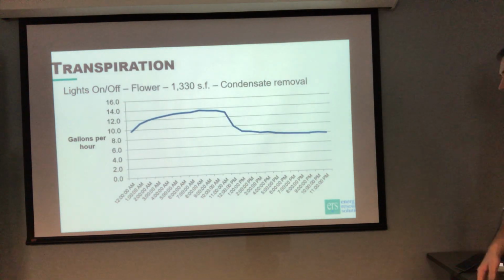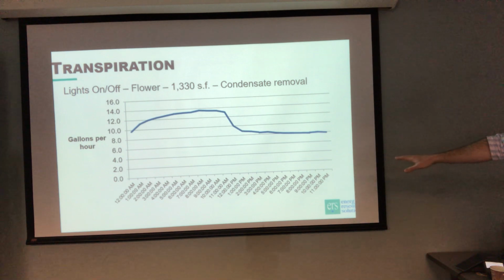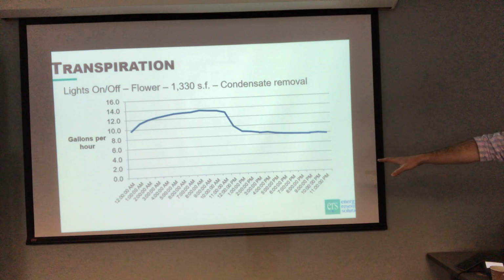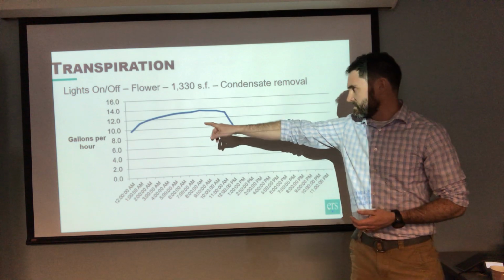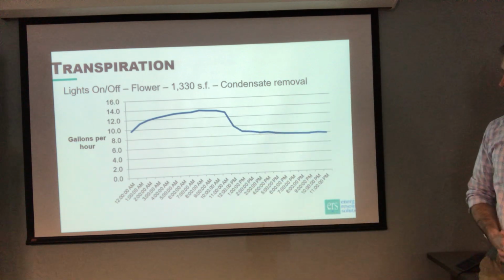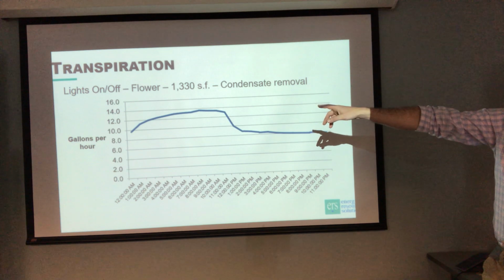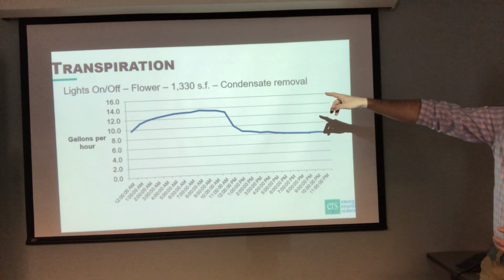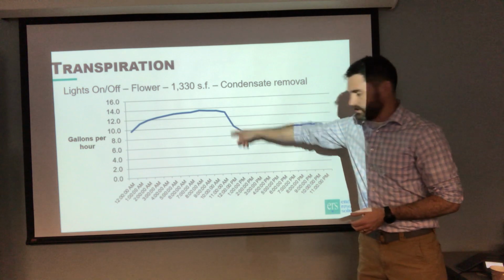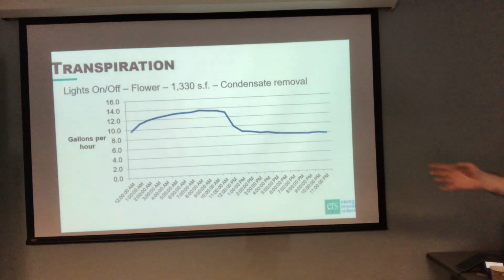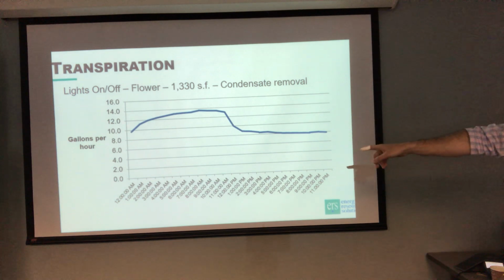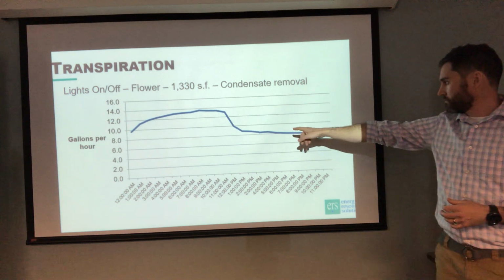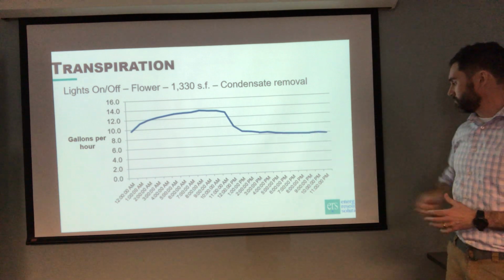So what does that transpiration look like? Again, this is real meter data from a facility that we worked on. This is a 1,300 square foot flower room. This is the average across 1 month towards the tail end of the flower cycle. You can see here, this is gallons per hour on the left, time of day on the bottom. They start off at about 10 gallons an hour, 12, 14, 16, peaking just around 14, and then what do you think's happening right around here? Exactly, the lights go off, and we can see that the transpiration drops rapidly, but it doesn't stop, it doesn't go away. We're still removing 8 gallons an hour from this space.